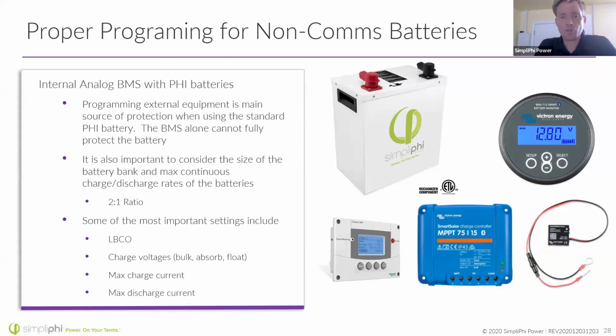Those are the voltages used during the charging cycles. The bulk part of the charge cycle is that constant current part. The absorb portion of the cycle is just 6 minutes where you're topping off at 56 volts. That's where you go from 90%, 95% state of charge to 100. It's also where most of the balancing is occurring. And then the float is just a very slow charge where sometimes it's in a charge cycle. And if you have a renewable energy source like solar, you could float at 54 volts.